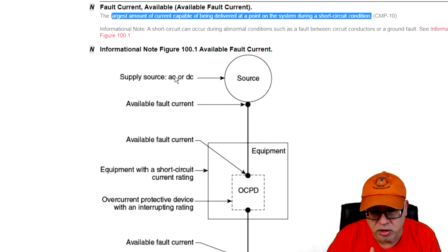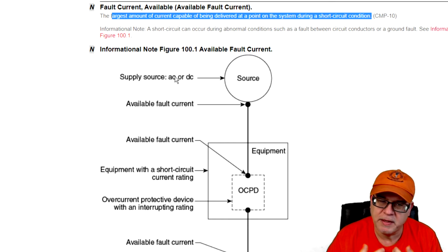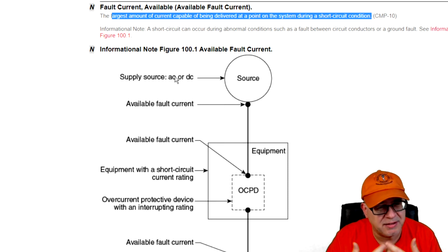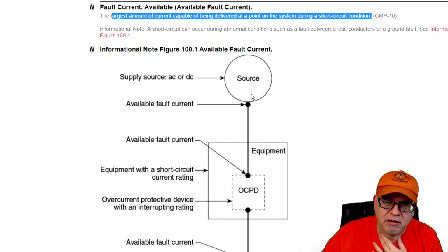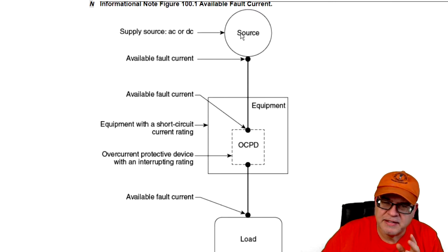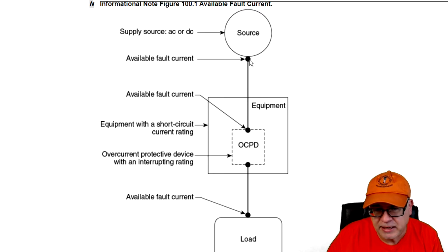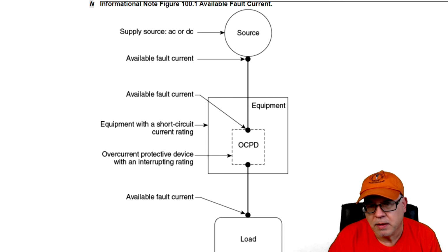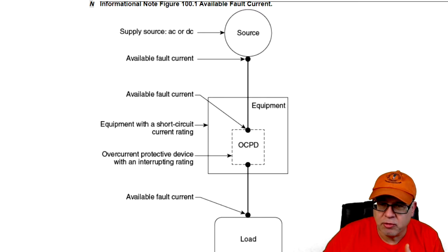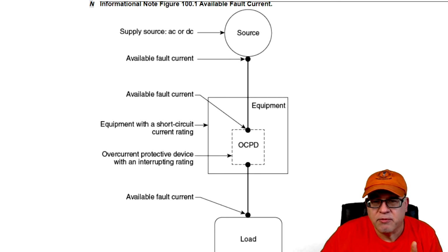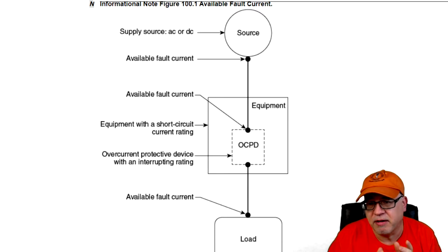So in our case, a fault current is the value at any point, okay? But then the available fault current is actually going to be the value that we work with when something says in the code that I need to know what the available fault current is. So where is that on the system? As you can see in this diagram, you have the source. And the source can be AC or DC, doesn't really matter. So say this is a utility transformer, and they're going to tell you what the actual available fault current is at the secondary of that transformer. Now, you need that because you have a certain distance of wire from that point into and up to the equipment. Now, most times you won't know fully, so you'll calculate something based on an infinite bus or whatnot, but usually the utility will give you these values in this scenario, what it is at the secondary.